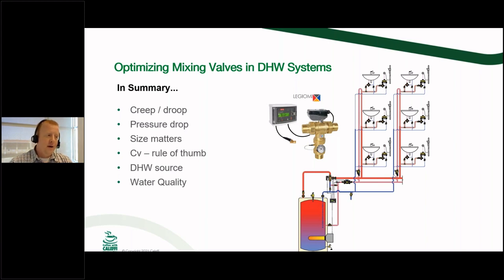to the other. Now, it's still not going to help that mixing valve work any better if there's a huge difference between hot and cold pressures. You know, say it's 60 on one side and 20 on the other side. It's not going to help that scenario, but it's going to prevent the migration from one side to the other. Is that a good answer there? Yeah, I think so. Unless there's like a copper shaving holding up that check valve, or something, and it's not seating properly, that could be an issue that you'd have.